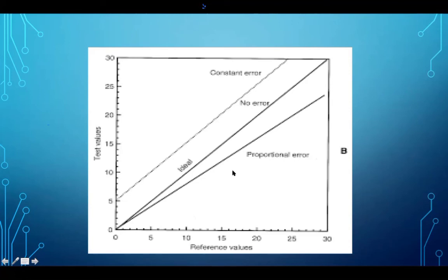So we have to document this. For this, what we do generally, we use calculator provided in the Westgard website. When we submit result of both the machines, it calculates one R2 value. This is called correlation coefficient. If it is more than 0.9, this is a good correlation. More than 0.95, excellent correlation. It should be close to 1.